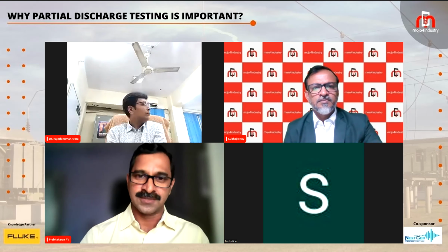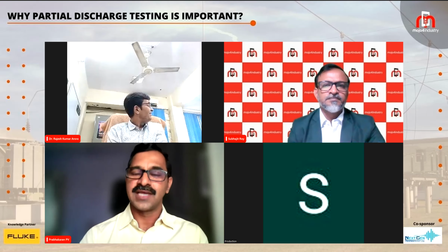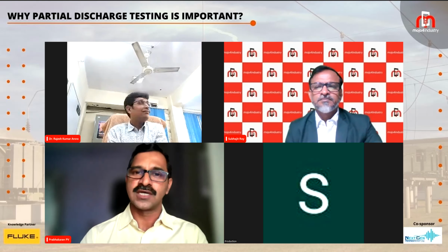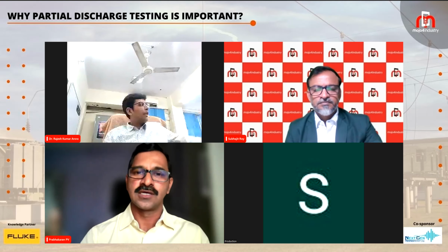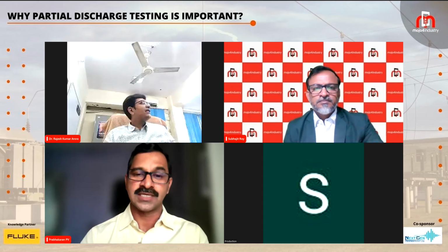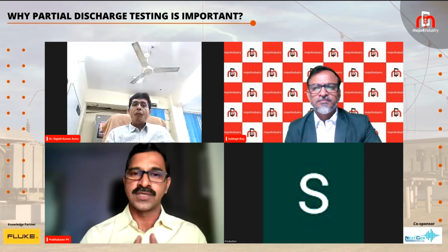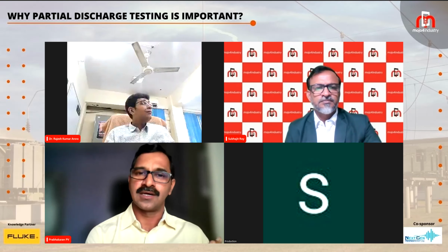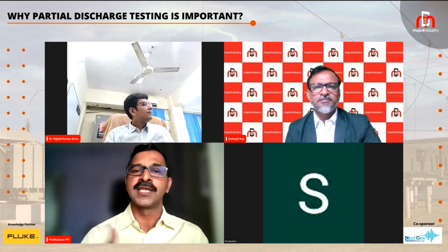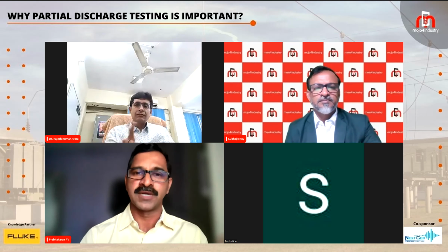That's actually difficult. Similarly, the acoustic system can give you most of the partial discharge information without touching the equipment, or at a safer distance. That's why acoustic is becoming more and more preferred for maintenance purposes, for predictive maintenance or actual condition monitoring.